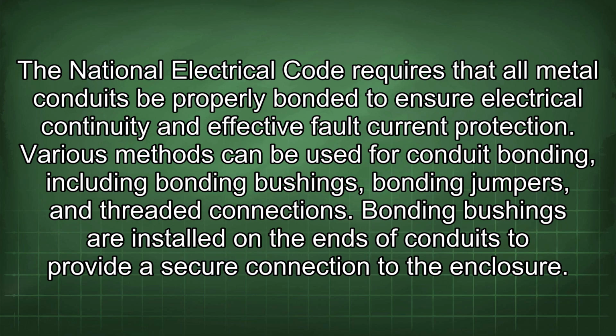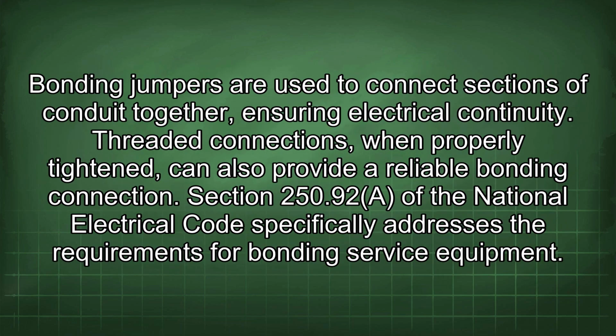Various methods can be used for conduit bonding, including bonding bushings, bonding jumpers, and threaded connections. Bonding bushings are installed on the ends of conduits to provide a secure connection to the enclosure. Bonding jumpers are used to connect sections of conduit together, ensuring electrical continuity. Threaded connections, when properly tightened, can also provide a reliable bonding connection.